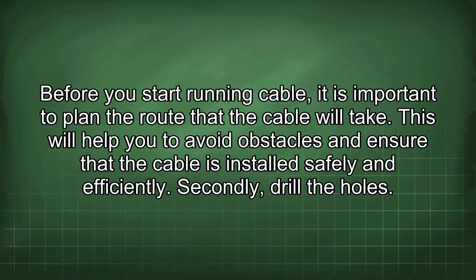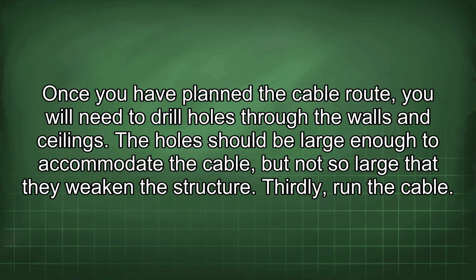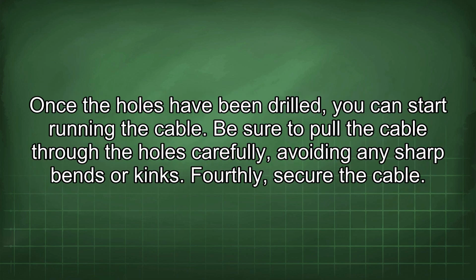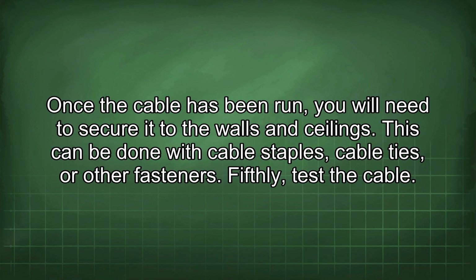Secondly, drill the holes. Once you have planned the cable route, you will need to drill holes through the walls and ceilings. The holes should be large enough to accommodate the cable, but not so large that they weaken the structure. Thirdly, run the cable. Once the holes have been drilled, you can start running the cable. Be sure to pull the cable through the holes carefully, avoiding any sharp bends or kinks. Fourthly, secure the cable. Once the cable has been run, you will need to secure it to the walls and ceilings. This can be done with cable staples, cable ties, or other fasteners.